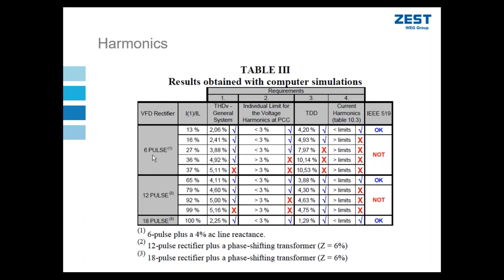Right. So comparing six pulse drives, if we placed in an installation only six pulse VSDs on that 8 MVA transformer, and 13% of its load was supplying six pulse VSDs, we would easily meet the requirement for THDV with no additional harmonic mitigation, no harmonic filters, no phase shifting techniques. And the same can be said for increasing that load right up to 36%. Even if 36% of that 8 MVA utility transformer is loaded with six pulse VSDs, I still come in below the 5% limit of IEEE 519. If I start loading that 8 MVA transformer more than 36% with VSD loads, then I start to have an issue.